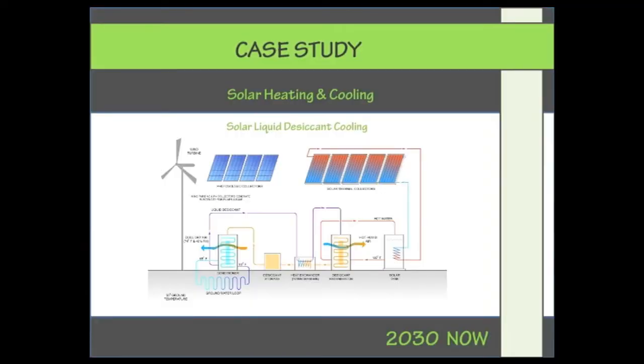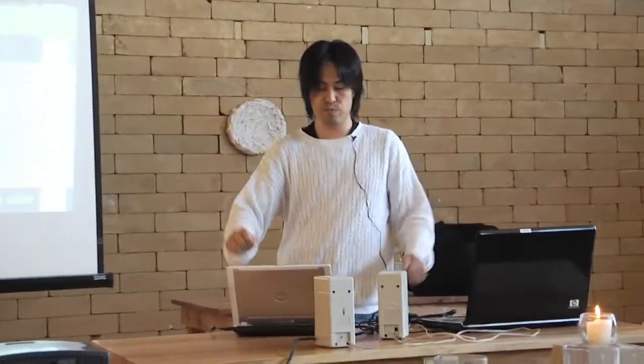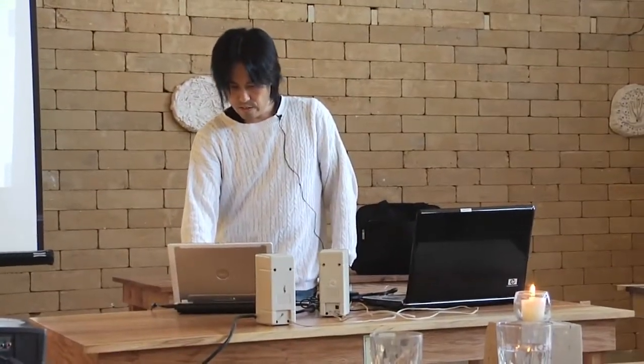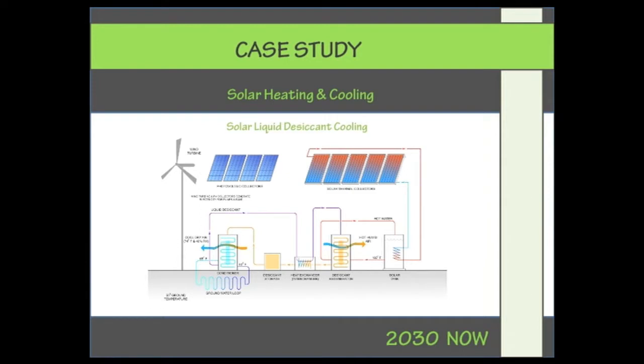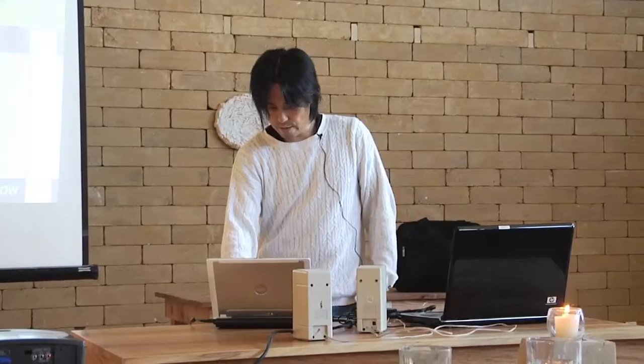And then we also use a liquid desiccant storage, which can store more energy, with only one-tenth of the capacity compared to hot water storage. So if you need 700 gallons of hot water storage, you only need 70 gallons of liquid desiccant storage, because you are storing energy as latent heat, not sensible heat. So you don't need a huge storage space. And it's really efficient because it doesn't have a heat pump. It runs only 2 kW for the total building system. The temperature requirement is only 160 to 180, which can come from a regular solar thermal panel. You don't need a high temperature solar system for this one.